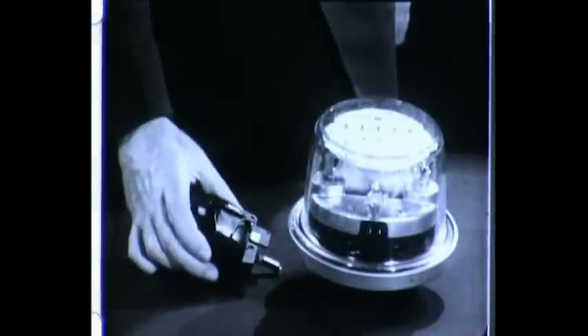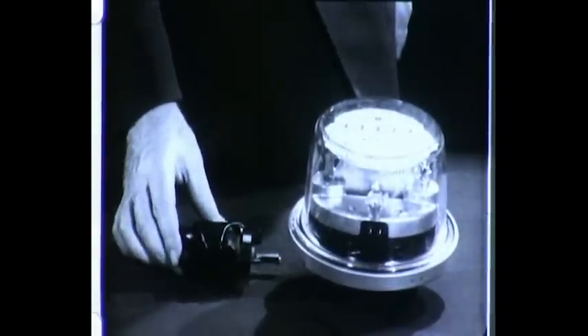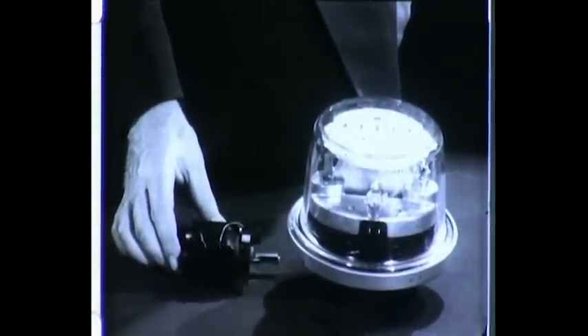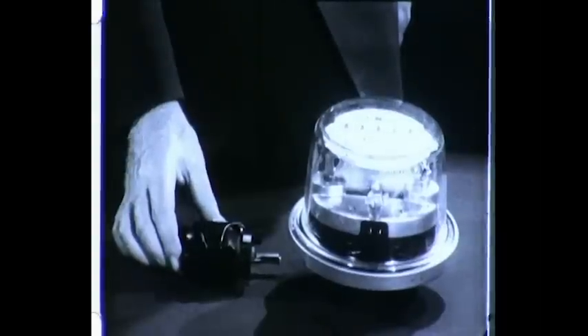The new I-60 provides a Class 200 meter at a cost no greater than the cost of existing Class 100 meters. This distinctively new I-60 meter features a revolutionary new stator design which assures greater sustained meter accuracy. The new design brings about a reduction in the complexity of current coils, which allows complete mechanical isolation of the current coils from current laminations. New current coil leads are much more simplified than older designs and require less material. And the new stator design assures that the I-60 is inherently no more costly than existing Class 100 meters.